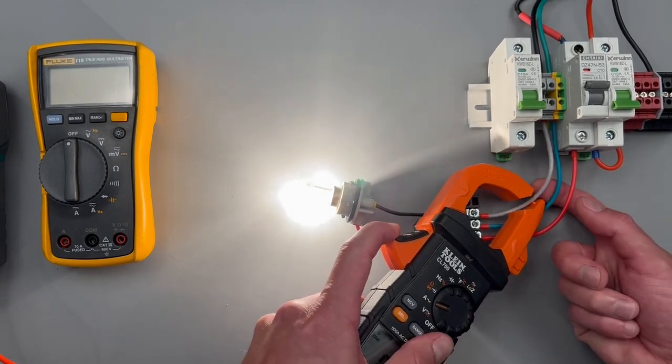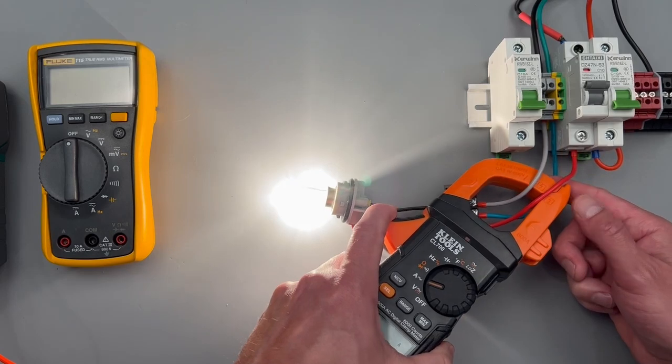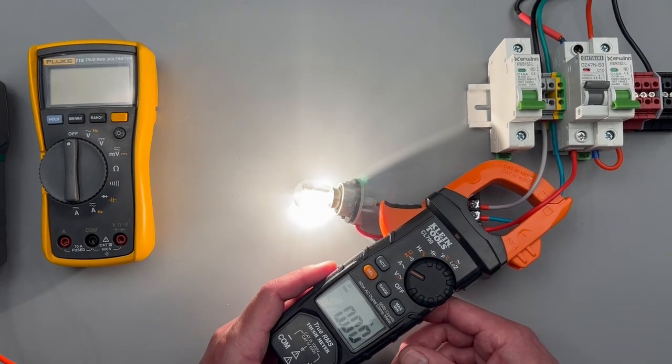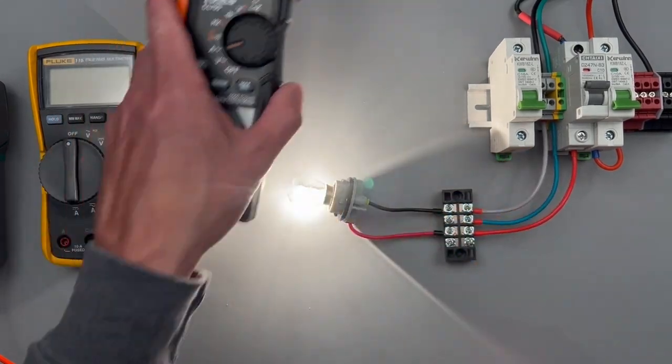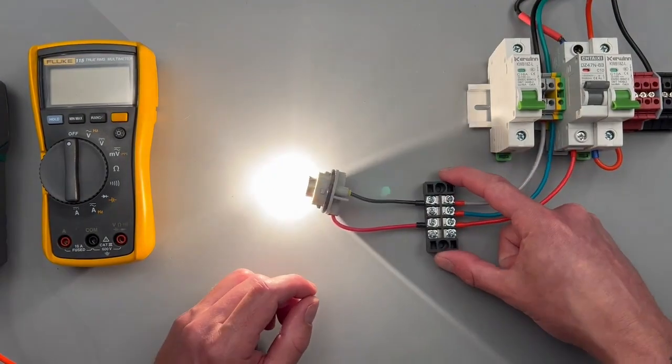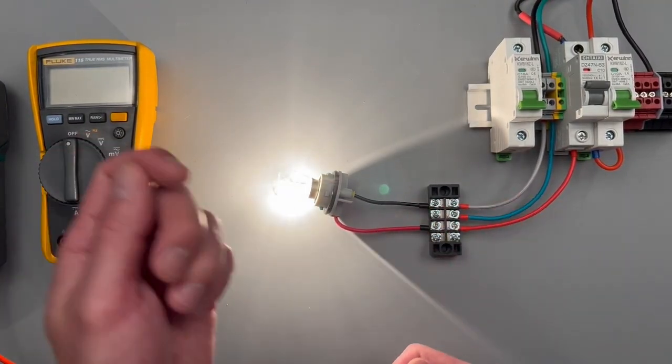Say I want to put it around an extension cord that doesn't have a separate neutral and hot—they're going to cancel each other out and it's going to come back at zero. If you're wanting to make a measurement with an amp clamp for something that's coming out of your wall, you'll want to look into something called a line splitter. That'll allow you to put the clamp around the neutral or the hot in a very safe manner.